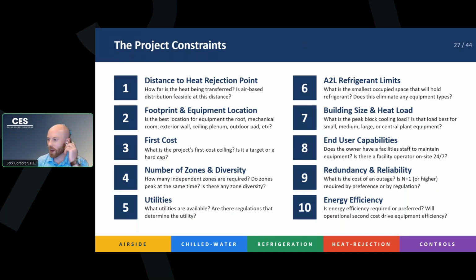First cost, rooftop units are typically very cheap systems, right? They're simple, they're easy, they're all packaged in one unit. That's a very powerful tool for them. The number of zones and diversity. As we said, your VAV system could potentially handle it, but what happens if part of your building needs to be cooling and part of your building needs to be heating? You're going to run into trouble running your rooftop unit for both of those zones because it's not going to be able to do both at the same time. You can either do one or the other.